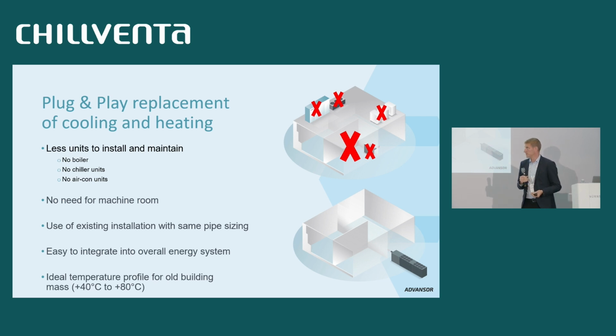We can keep the same installation in the building. So if we can deliver the same temperature as a gas boiler, then we can keep the same pipe systems, the same radiators, the same ventilation systems, coils, pumps and so on. And with our heat pump, we have an open Modbus protocol, meaning that it's easy to integrate into the overall BMS or SCADA system of the building. On top of that, we also have the possibility to provide cold water for air conditioning or other cooling purposes.